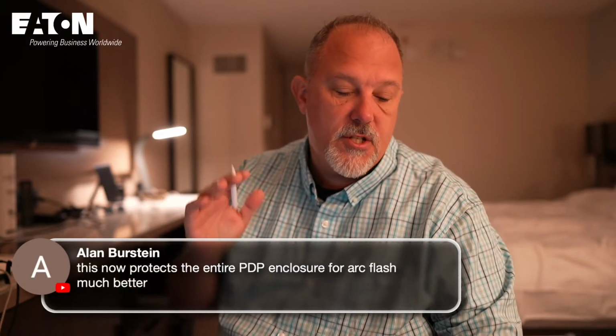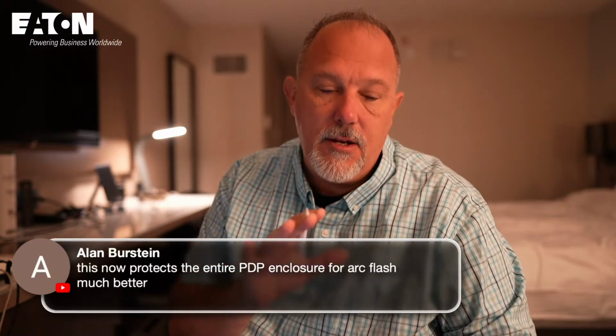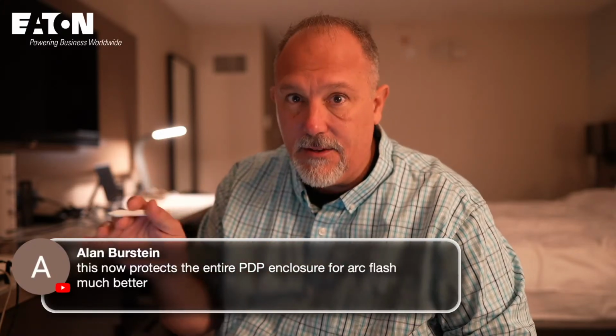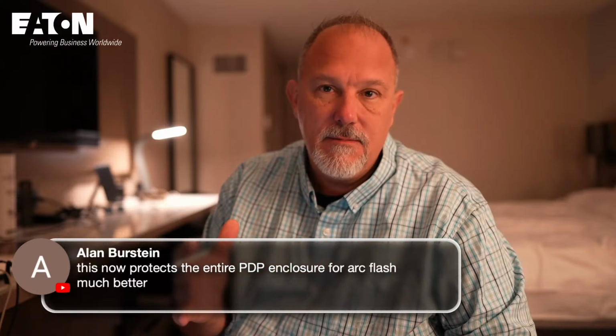Much better. So as long as we can pop that out, then you know what, Alan, the challenge then is, what's the price? And do I have the space? To your point, if I bring that into the transformer, then I don't have to necessarily worry about space. I should be able to reduce the price of that panel board, that 208 panel board, because I don't have a main. It's a main lug only panel board. But you need space and you need price, right?